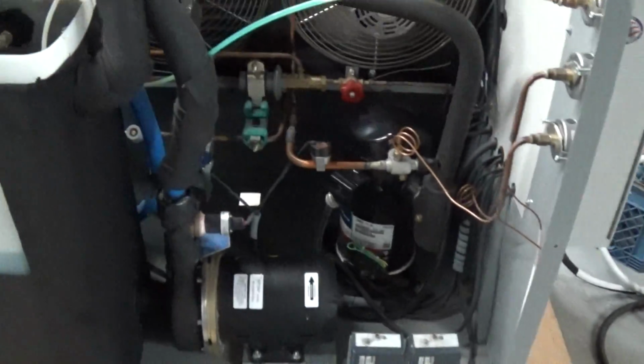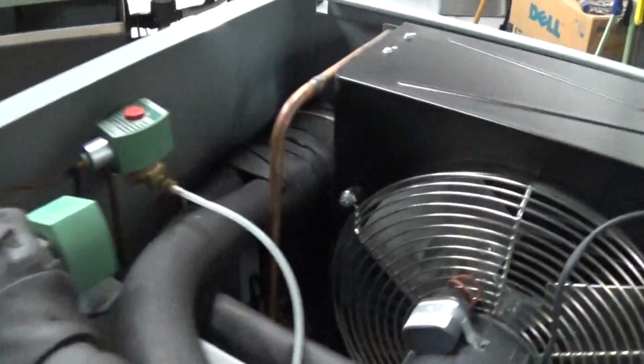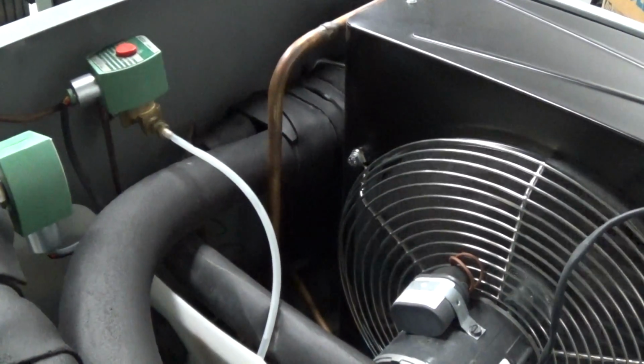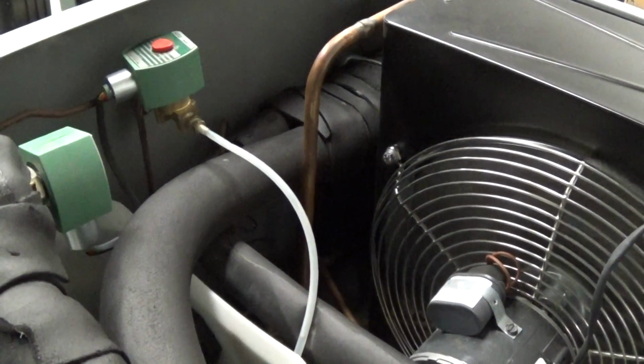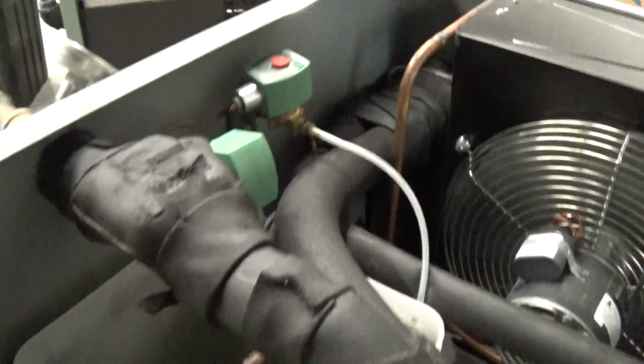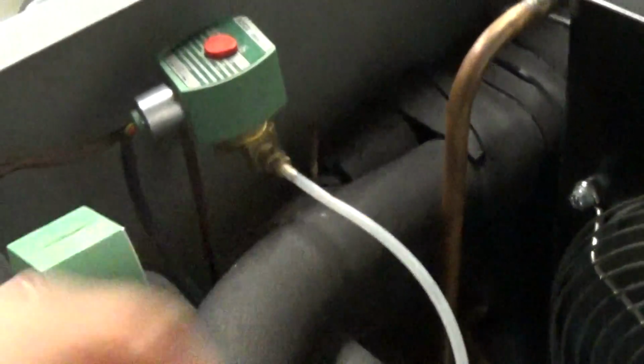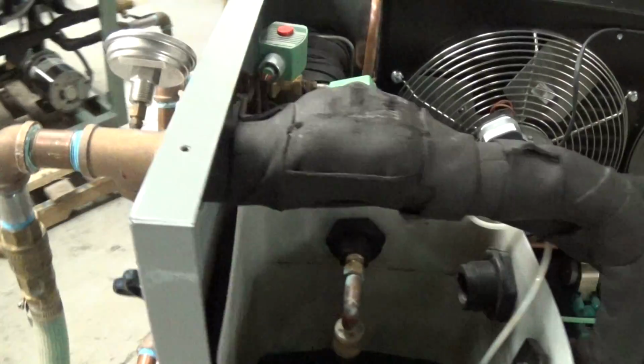We actually call Mokon about this unit, and they actually seem pretty good about supporting their used equipment. And this is not that old at all, but they're available, or you can go through Mokon. This here, if you choose to use it, this is a solenoid valve for water makeup. You can tie that in right here if you do want to do that. You don't have to. We're running it on partial amount of glycol. We have this level sensor and one down in there. When it gets lower than one particular number or limit, you'll bring in more fluid for the water makeup.